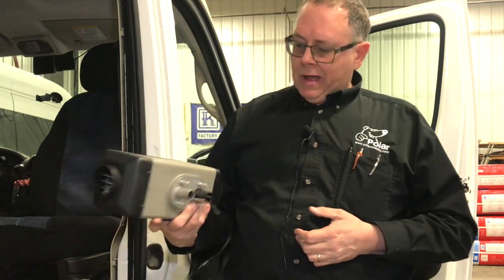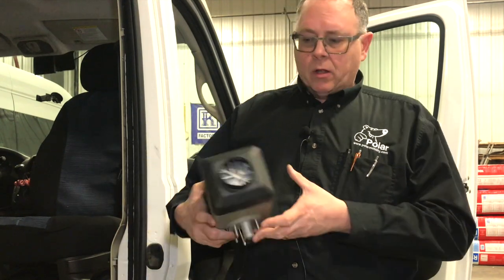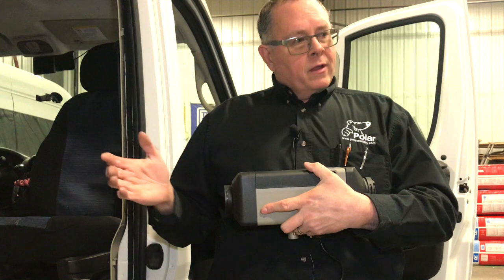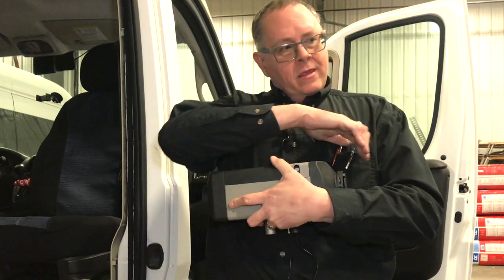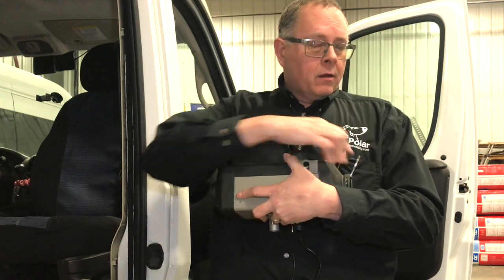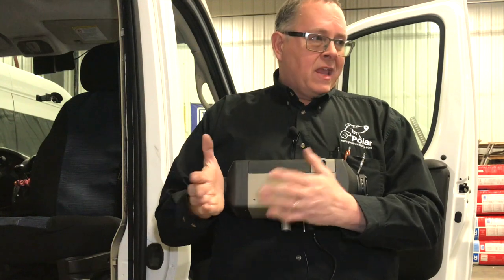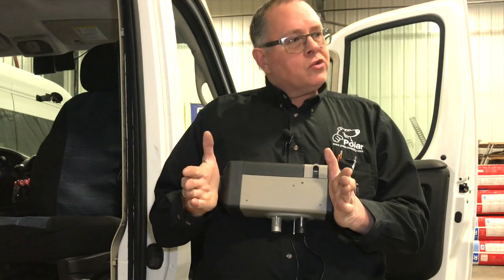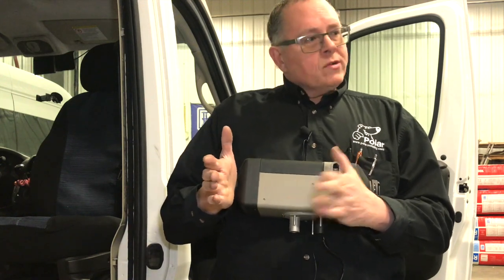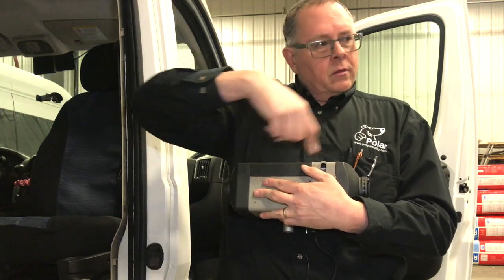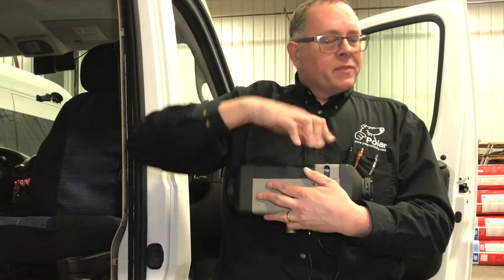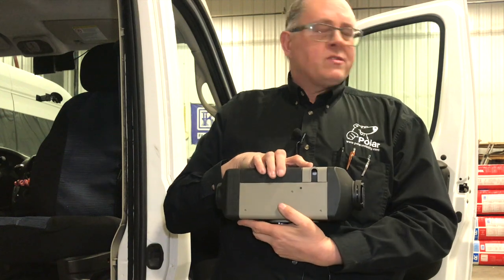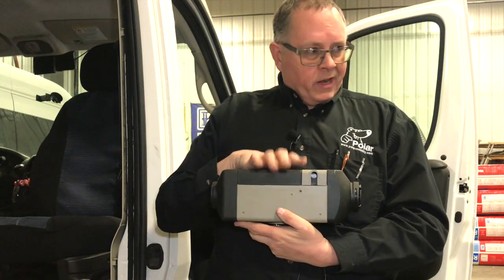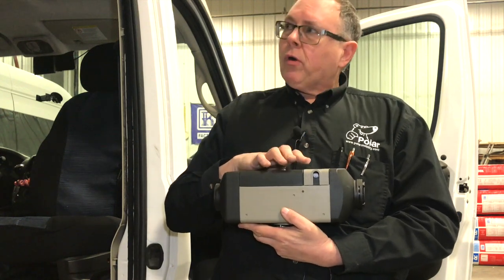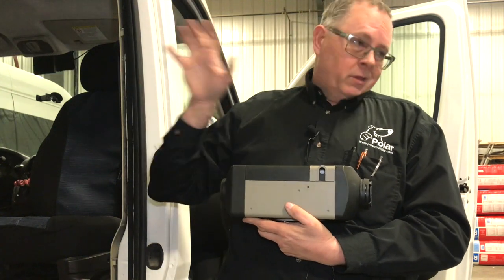When you mount it yourself and install it, don't ever have the heat and the return or process air coming out and facing in the same general area or location, because you'll have the heater short cycle. It'll only heat a very small area, and then you'll have problems with it prematurely shutting down, and it won't properly regulate the temperature in the entire space.